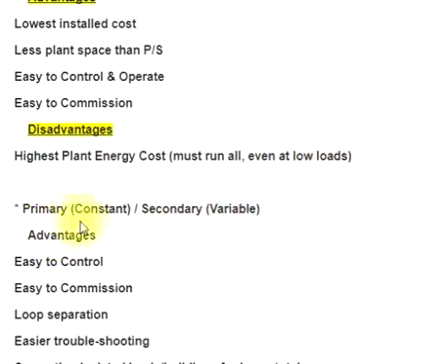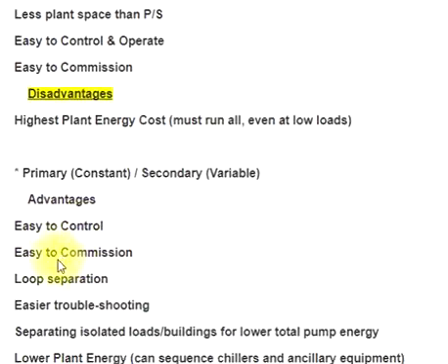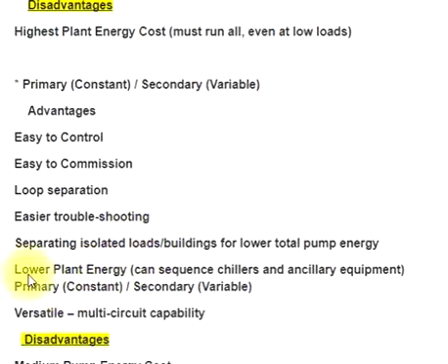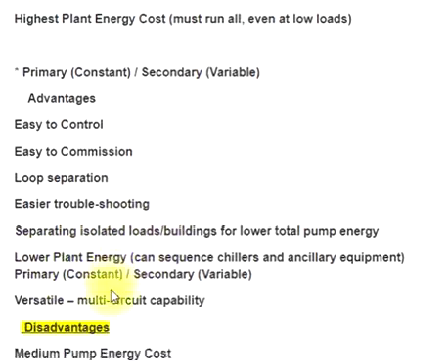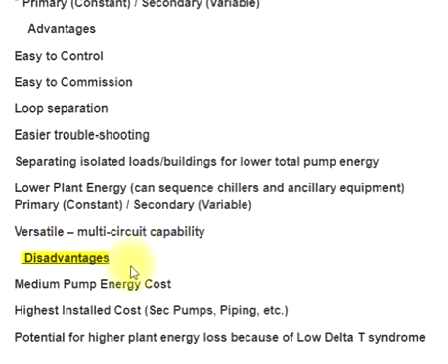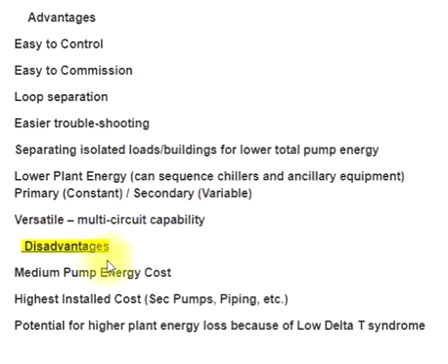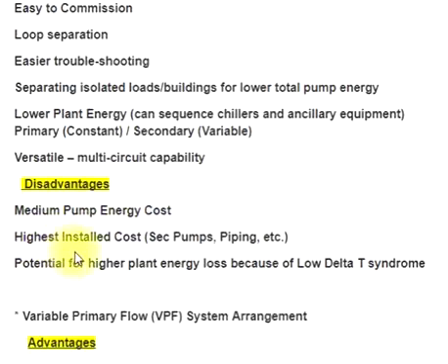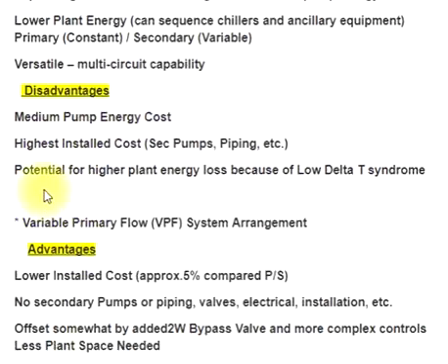Primary constant, secondary variable advantages: easy to control, easy to commission, loop separation allows easier troubleshooting and isolating separated loads and buildings, lower total pump energy, lower plant energy for chillers and ancillary equipment. Primary constant, secondary variable is versatile with multi-circuit capability.